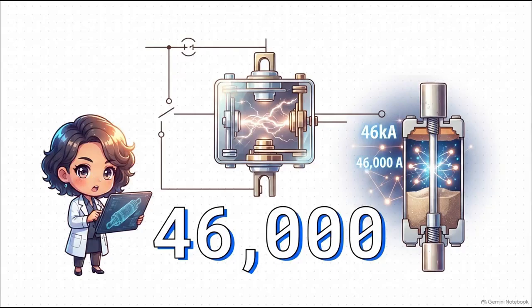And wrapping up our low and medium voltage circuits, we have the switch fuse. Just look at that number on the screen, 46,000. These switches usually come in units ranging from 30 up to 800 amperes, but their making capacity is massive, up to 46 kiloamps.